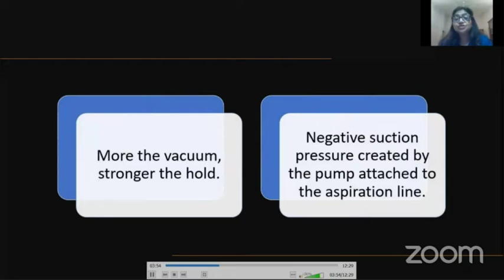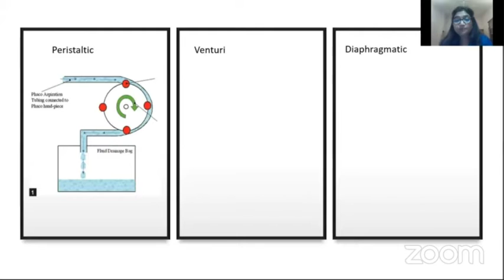Now, these pumps are either peristaltic, venturi, or diaphragmatic. It is the peristaltic which is most commonly used and safer because it has a pump with rollers, and when the aspiration tubing goes over these rollers, it pinches the tubing and helps in milking the fluid forward. And when the flow rate is high, this pump will move faster.